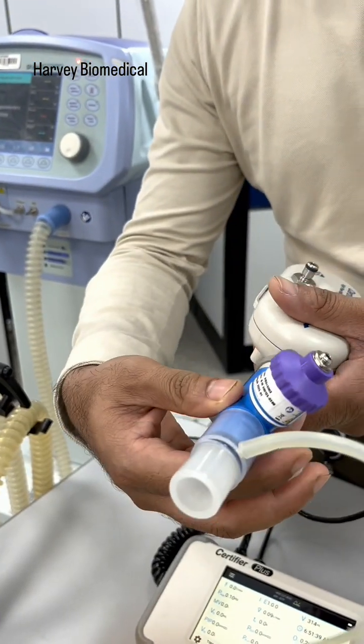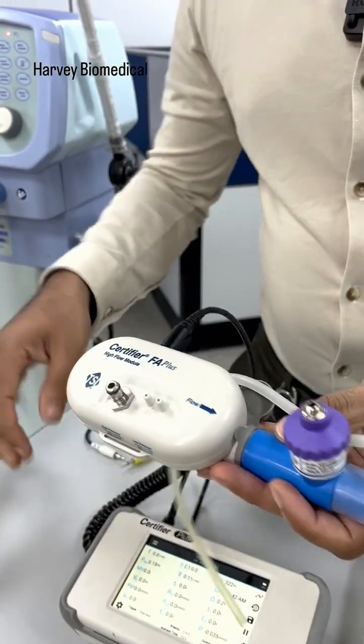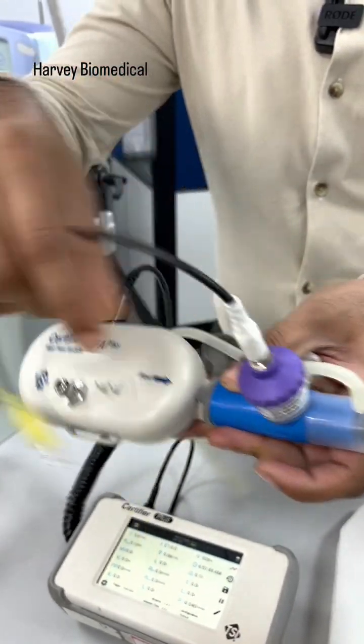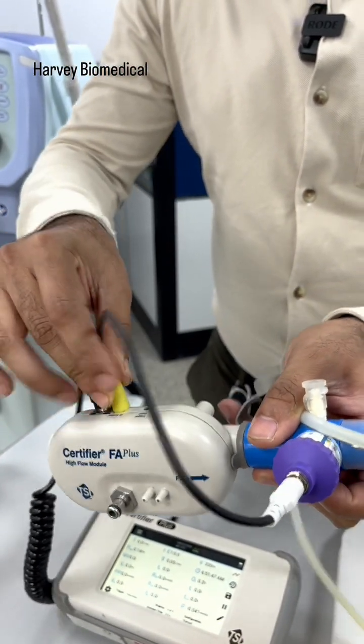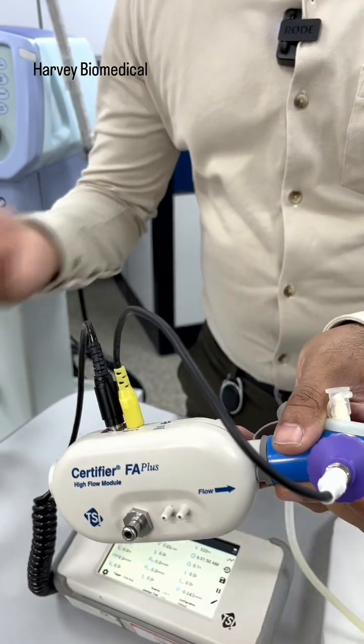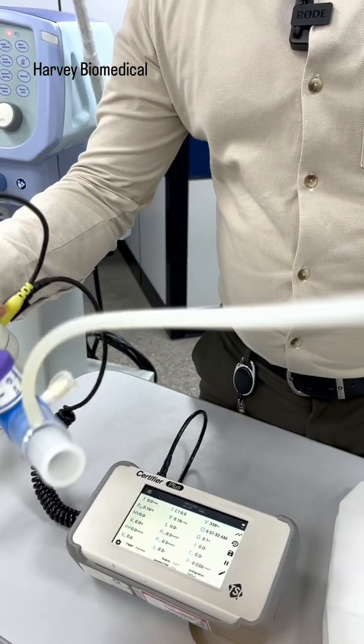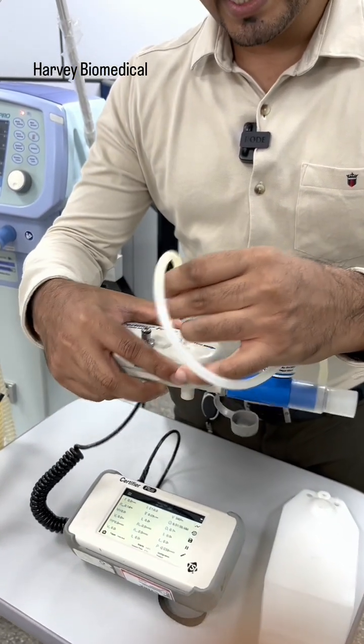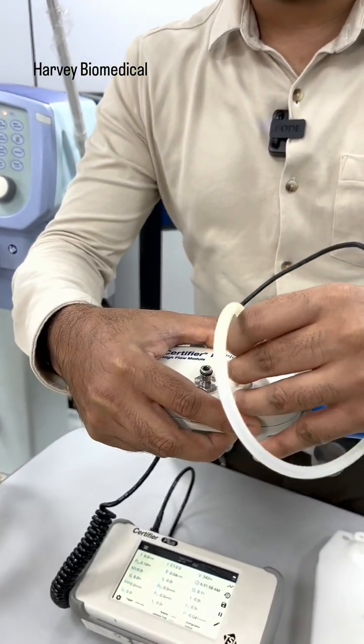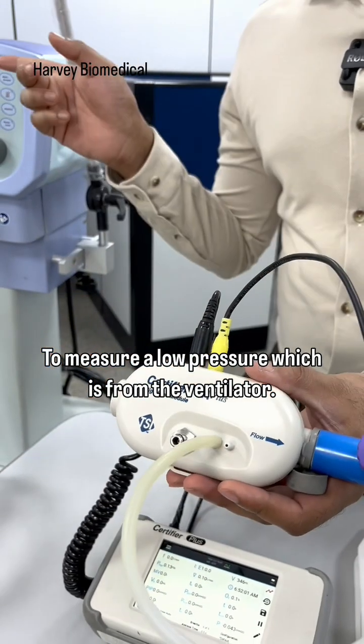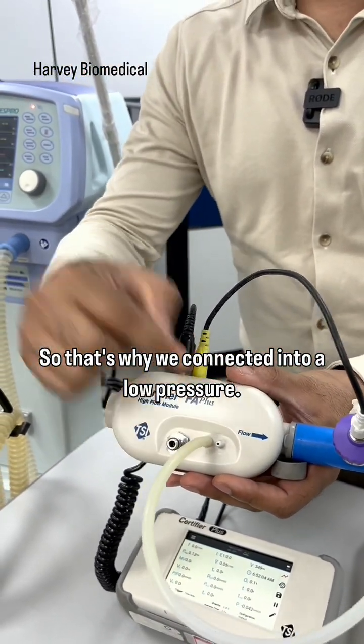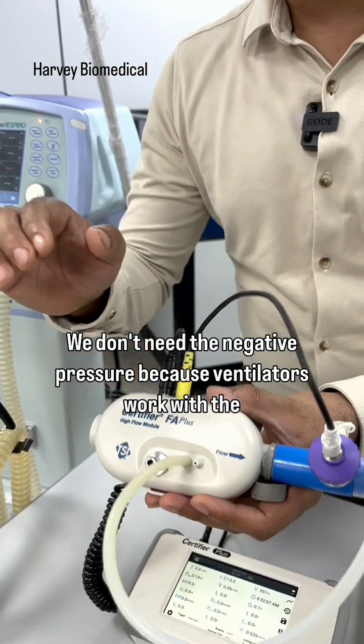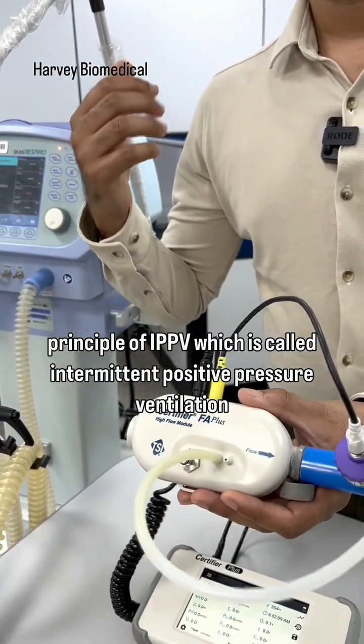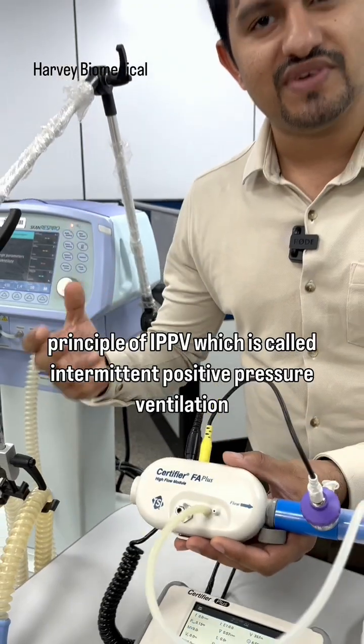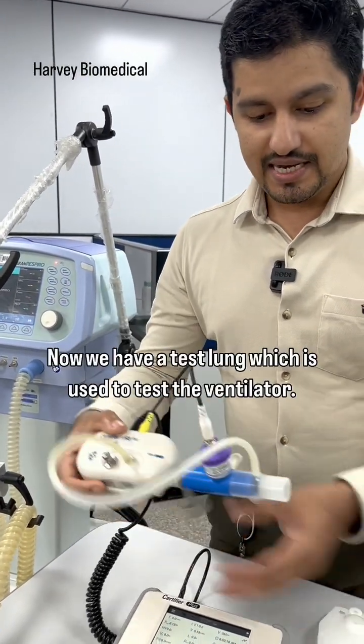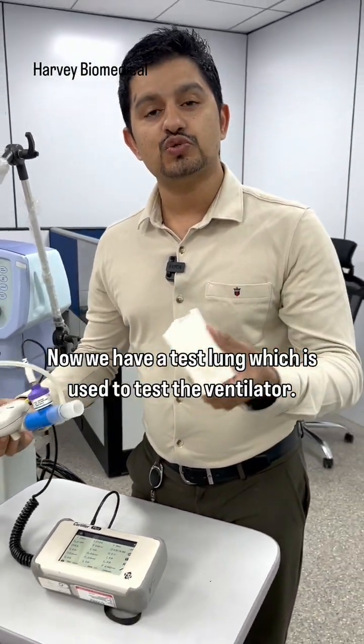Now we need to connect this oxygen sensor to the device here. And we have a tube here for the pressure sensing circuit, which I connect to the pressure sensor over here, because we are going to measure a low pressure from the ventilator. So that's why we connected it to the low pressure, positive pressure. Negative pressure is there, but we don't need it because ventilators work on the principle of IPPV, which is called intermittent positive pressure ventilation, as you know. So it's connected here.